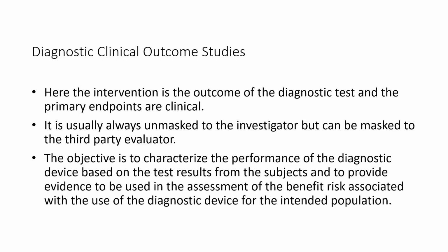So in diagnostic clinical outcome studies, right, where we are trying to diagnose certain things, and we just spoke about biosensors, for example, this is used for diagnosis. Here the intervention is the outcome of the diagnostic test and the primary endpoints are clinical, right? It is usually always unmasked to the investigator but can be masked to the third party evaluator, right? If you're doing a clinical outcome study, the objective is to characterize the performance of the diagnostic based device on the test results from the subjects and to provide evidence to be used in the assessment of the benefit risk associated with the use of the diagnostic device for the intended population.